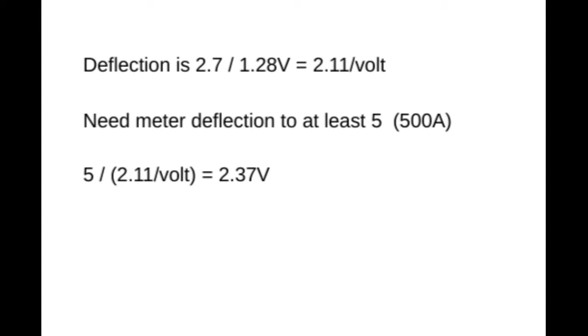Okay, so if the deflection is 2.7 at 1.28 volts, that's a deflection of 2.1 per volt. Now we expect a maximum current of about 400 amps, so we'd like the meter to go to at least 500 amps, that is 5 on the meter. So at 2.1 per volt, we'll need to energize the meter with at least 2.37 volts, and since it has a resistance of 165 ohms, that means 14.4 milliamps.